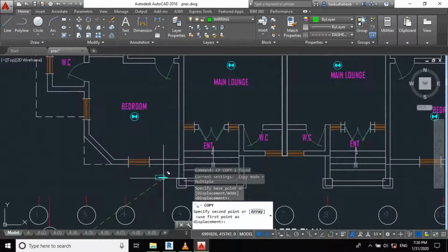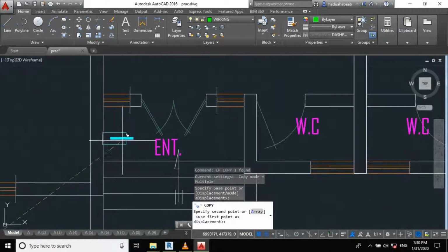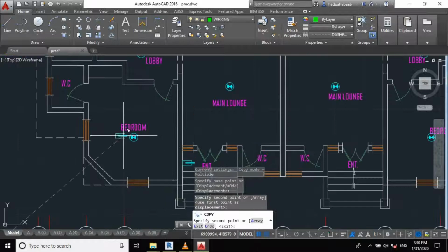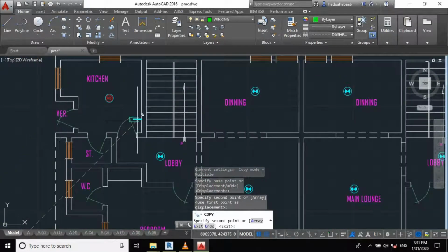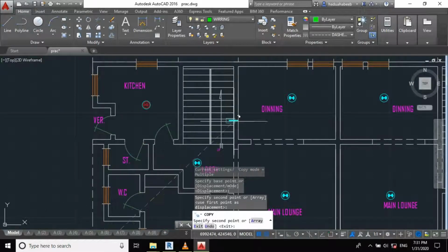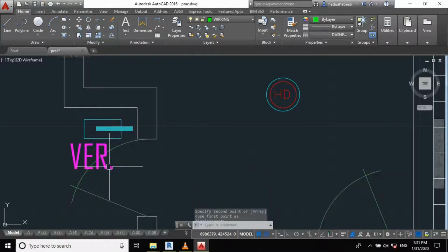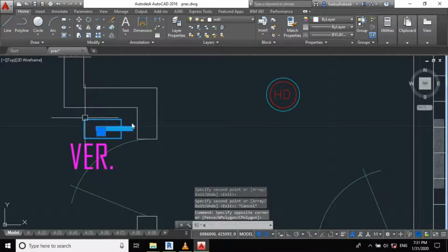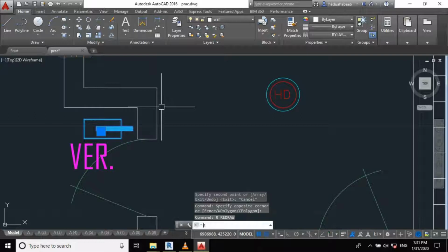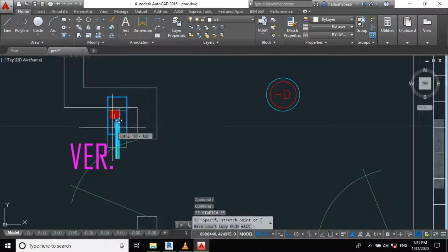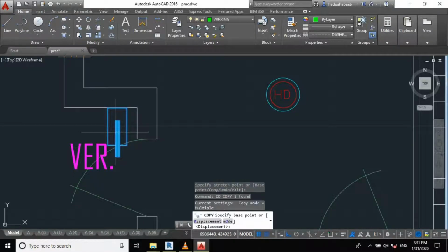And for our ground floor here, based on NFPA, it would be great to have one around the entrance. Let's choose this side. And likewise, we can have one because we are having another exit route here, which means occupants can pass through this to the exit. Because of that, we'll be able to have another manual call point here. Let's copy, let's go to the other floors.